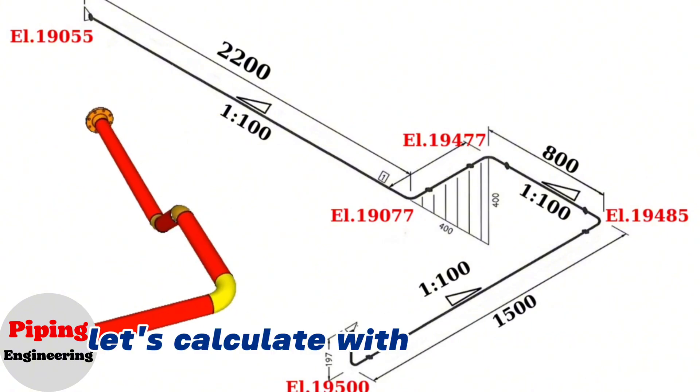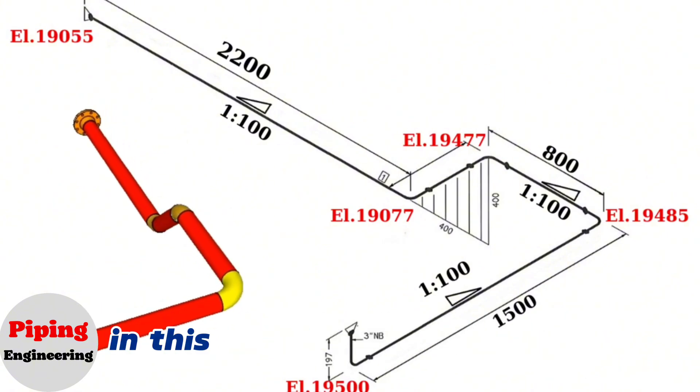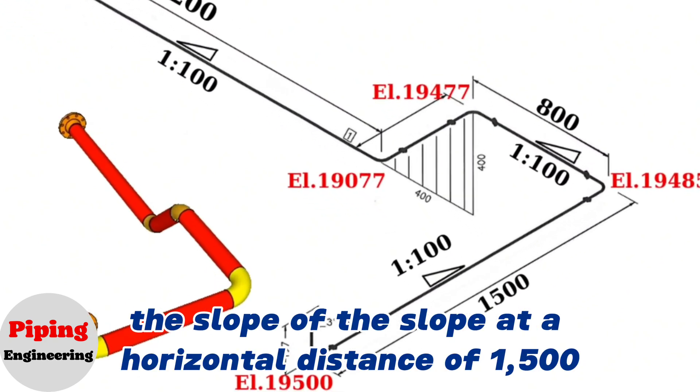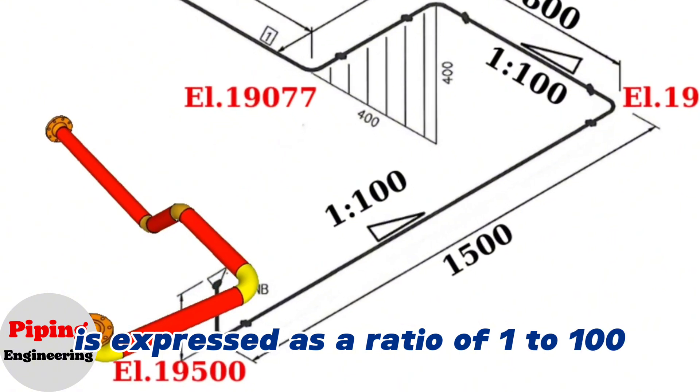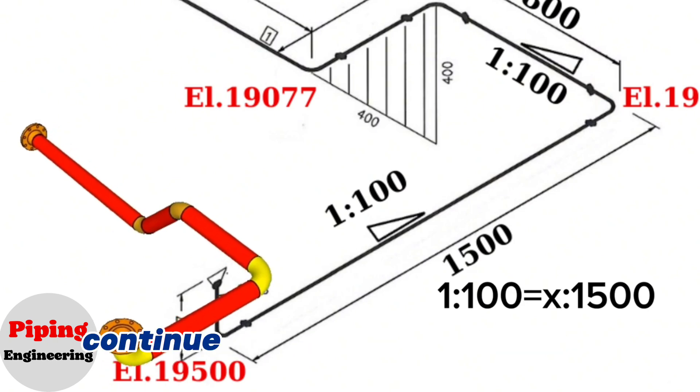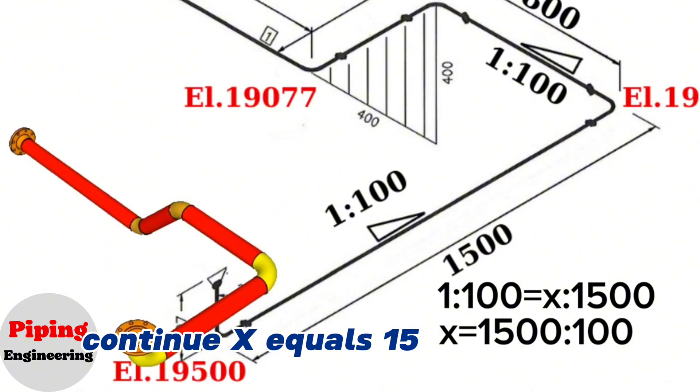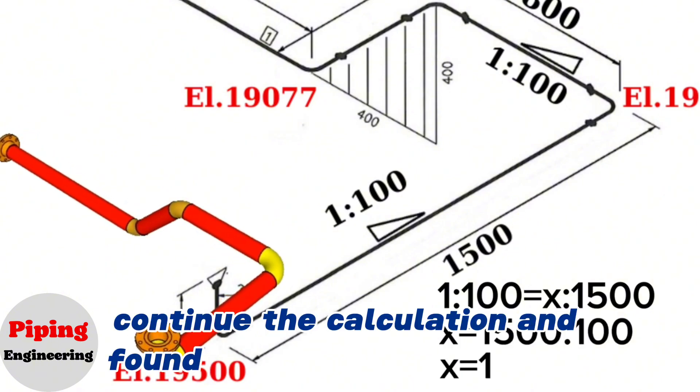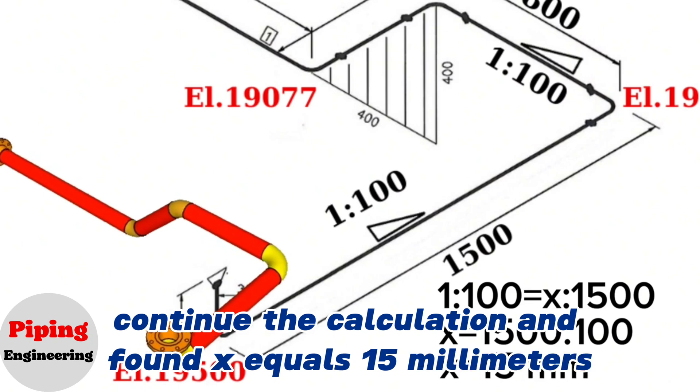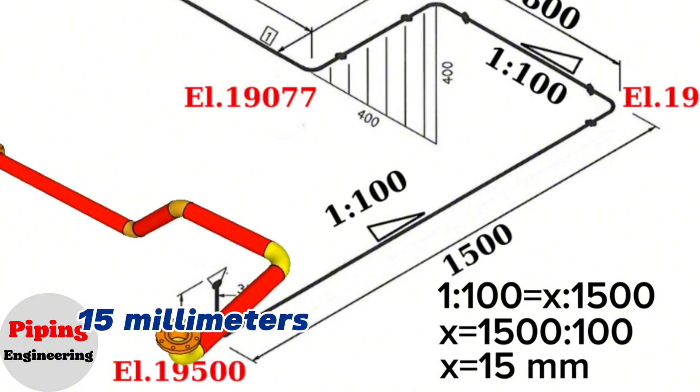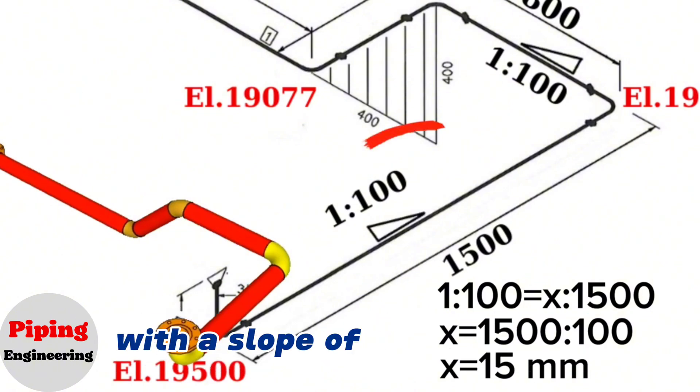Let's calculate with slope ratio in this example. In this pipe isometric drawing, the slope at a horizontal distance of 1500 is expressed as a ratio of 1 to 100. 1 to 100 ratio equals x to 1500 ratio. x equals 1500 to 100 ratio. Continue the calculation and found x equals 15 mm. This means that the 1500 mm long pipeline falls 15 mm down at the other end with a slope of 1 to 100 ratio.